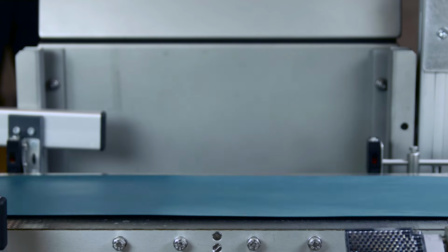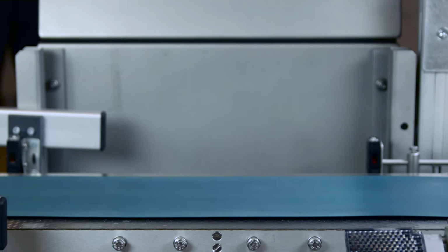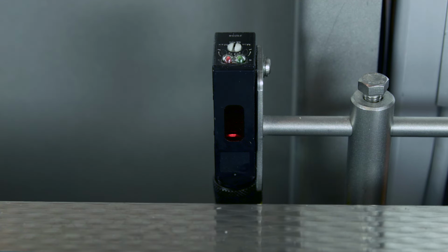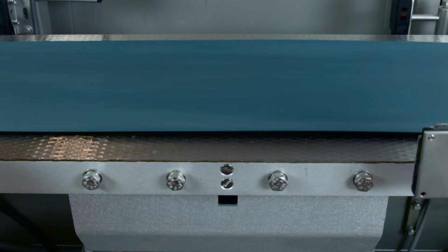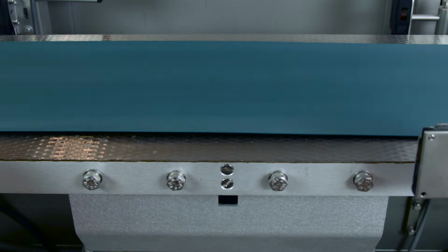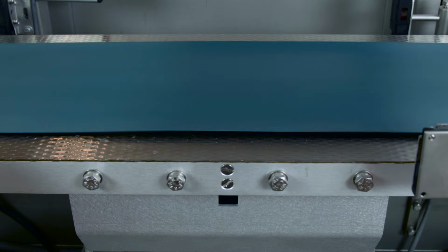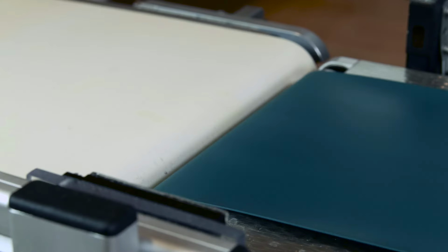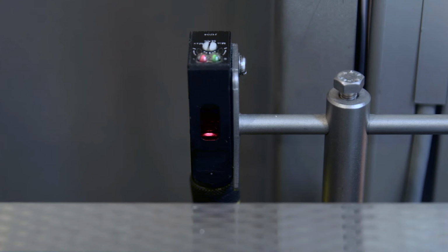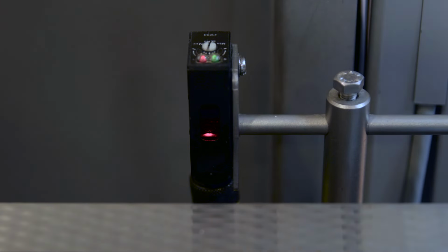In the next step, we will have to decide which area of our plateau we will use as the basis for our weight determination. We can then specify that area for FIT7A in terms of a triggering reference signal, a so-called trigger. The triggering condition can be the exceedance of a specified measured value, and it can also be an external signal, such as from a light barrier. We will use a light barrier for the purpose of this example.